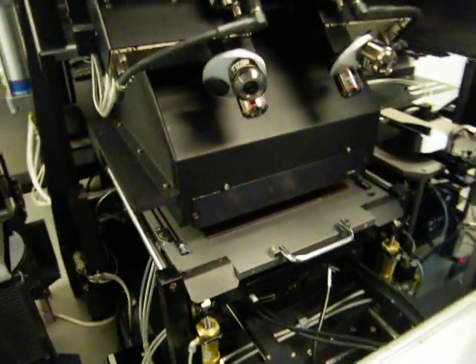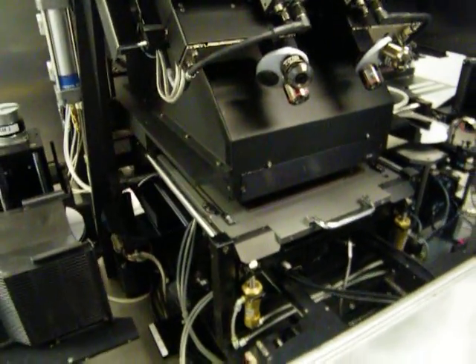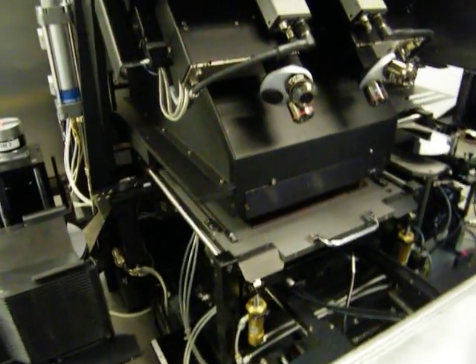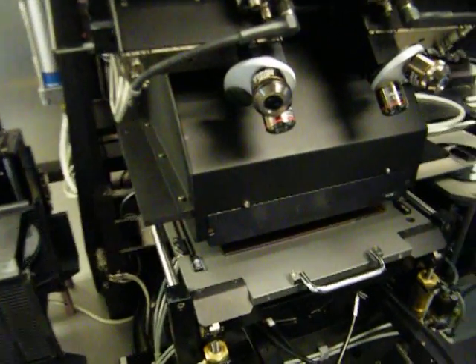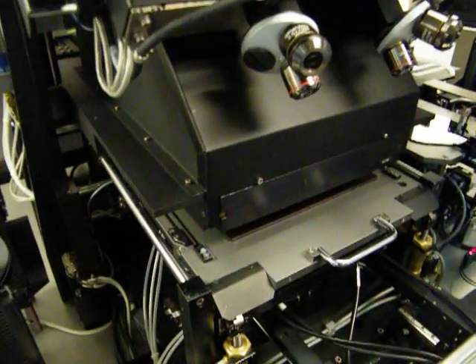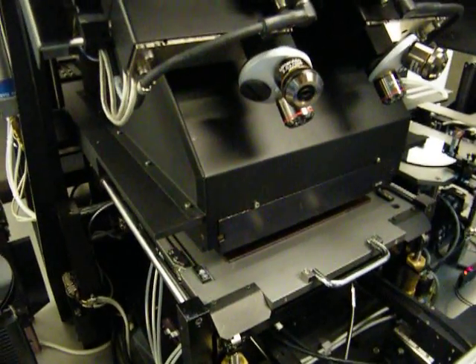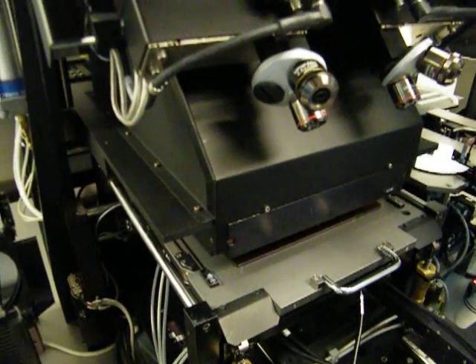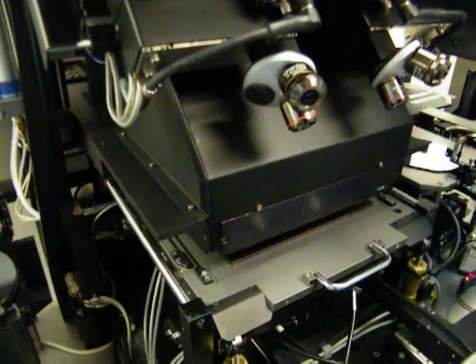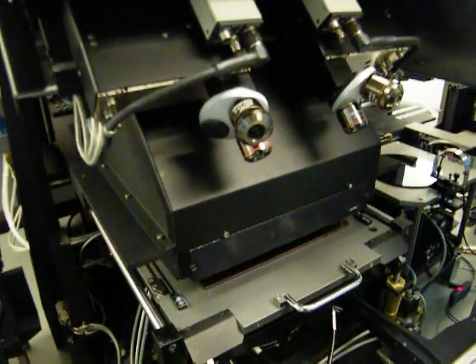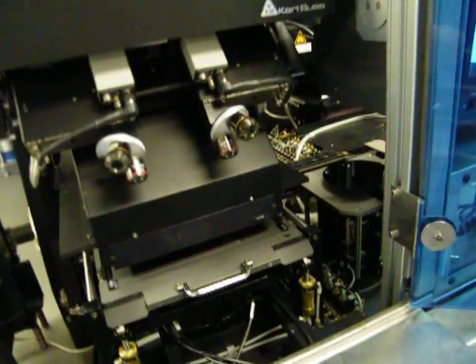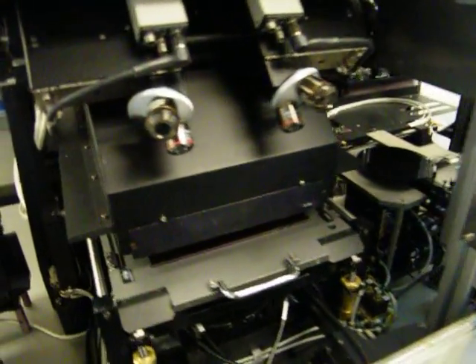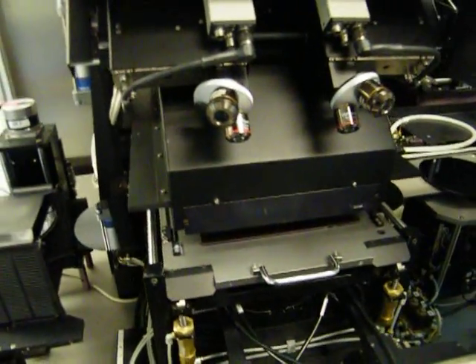Now just to explain, we have the lamp house, the shutter turning on and off, but as you've noticed, the UV lamp is not on. The tool has been, nitrogen has been turned off already in preparation for shipment. But you are hearing the shutter, and of course we have done the uniformity testing. It has been tested thoroughly. The uniformity is less than 1% over an 8 inch area, which is excellent.